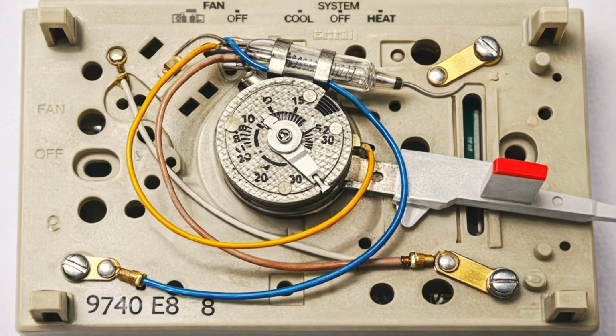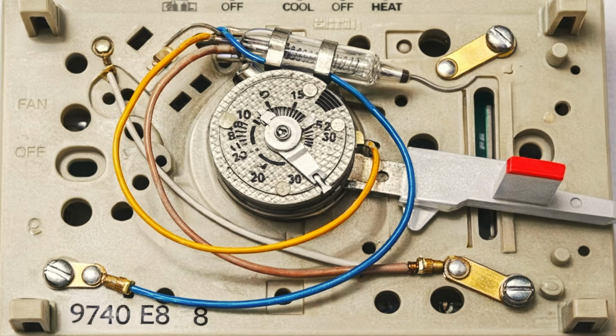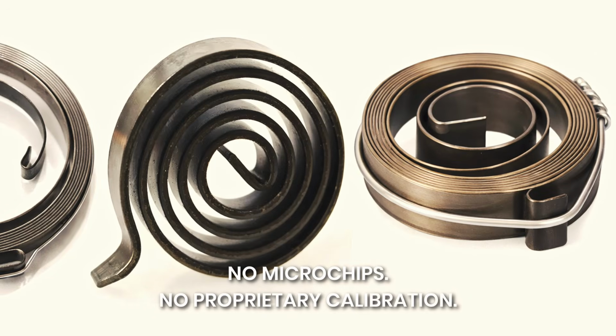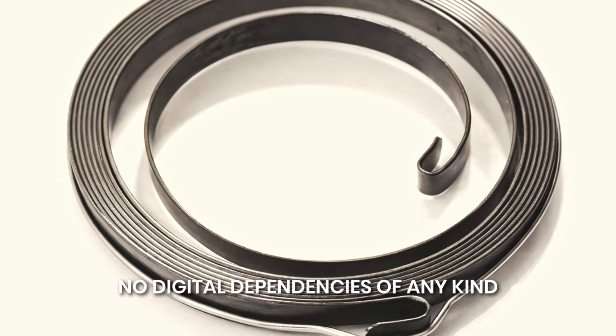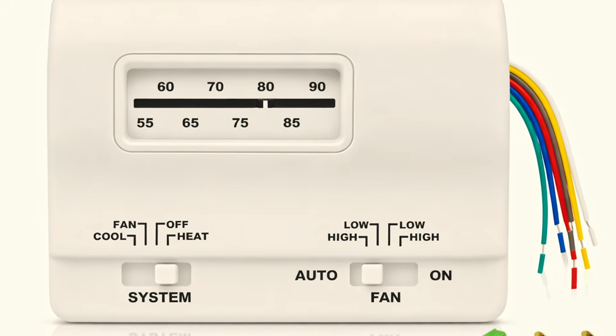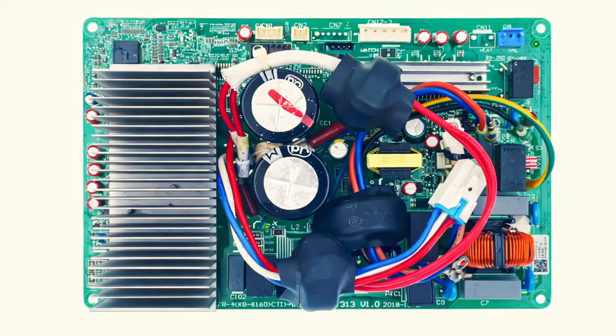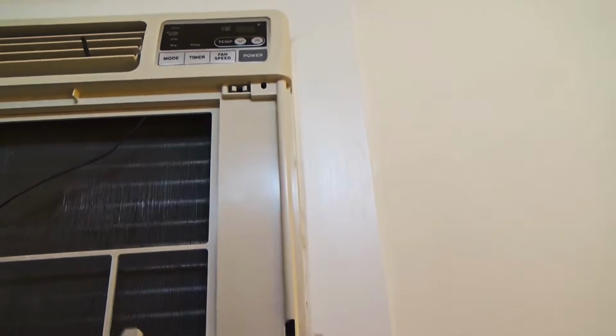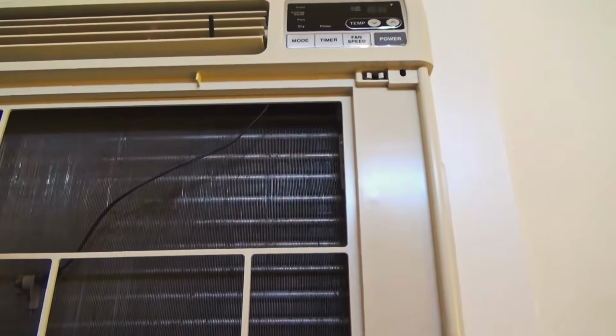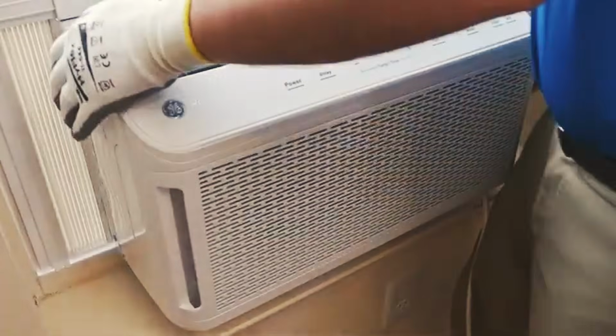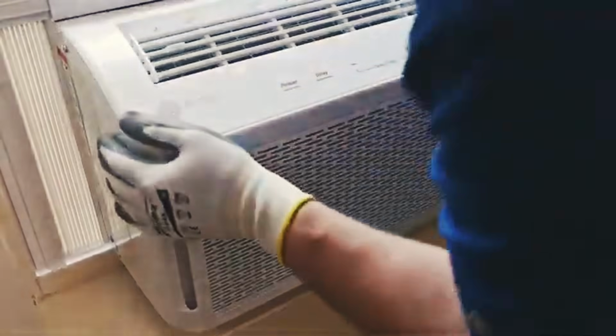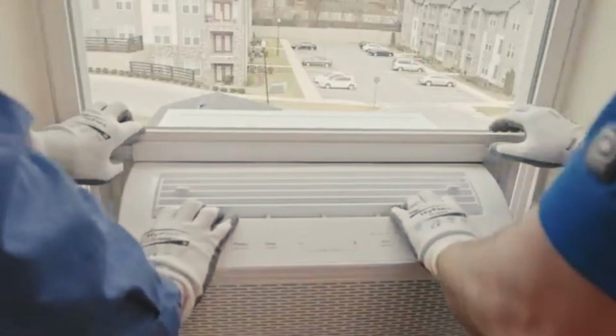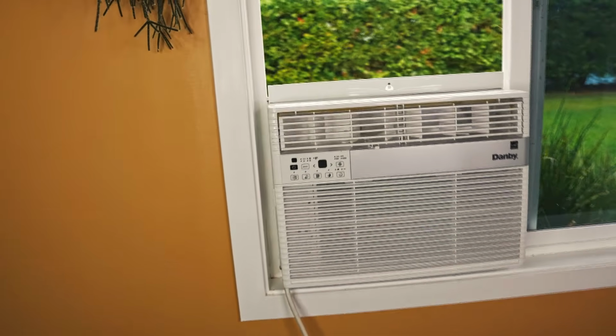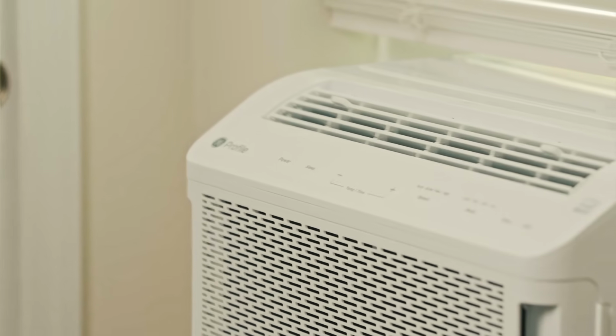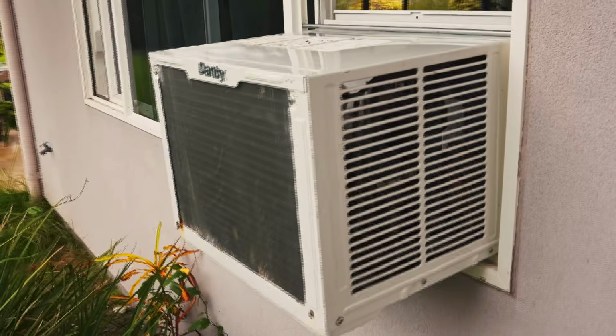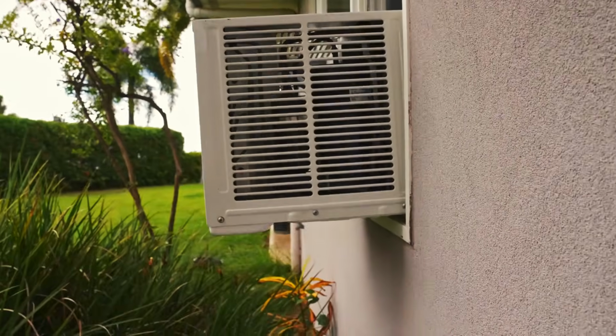First, the thermostat. The old bimetal mechanical thermostat was not sophisticated. It was nearly indestructible. No microchips, no proprietary calibration, no digital dependencies of any kind. Today, nearly every budget and mid-range window unit uses an electronic thermistor paired with a proprietary control board. The thermistor itself is cheap, a small component that changes its resistance with temperature, but it is calibrated to one specific board, unique to a model run that may have been on a retailer's shelf for two years before discontinuation. When the thermistor drifts out of spec, and it will, usually between year 3 and year 5, the unit begins short cycling. It runs for a few minutes, shuts off before the room cools, then kicks back on.